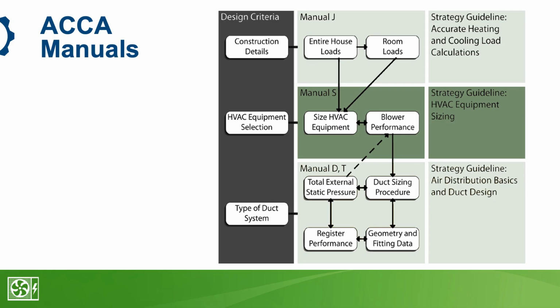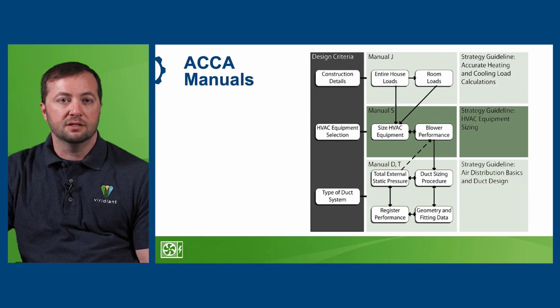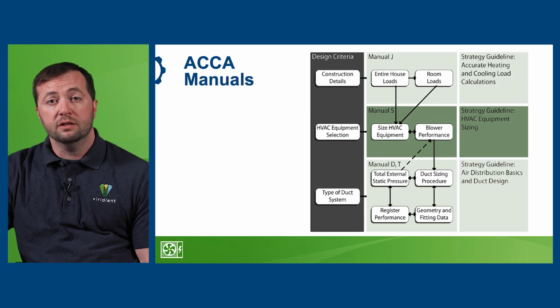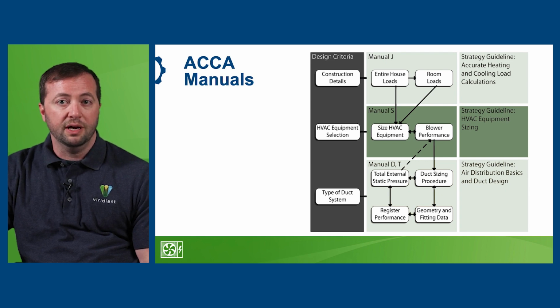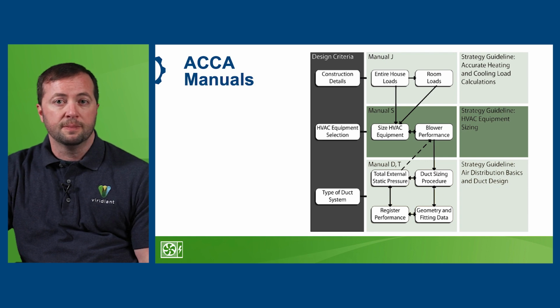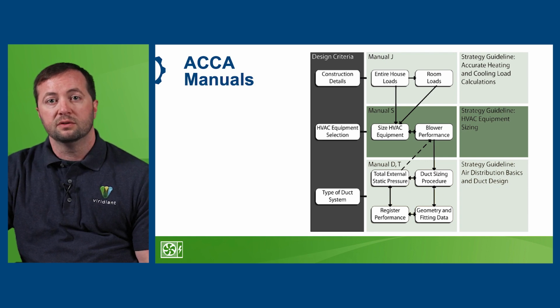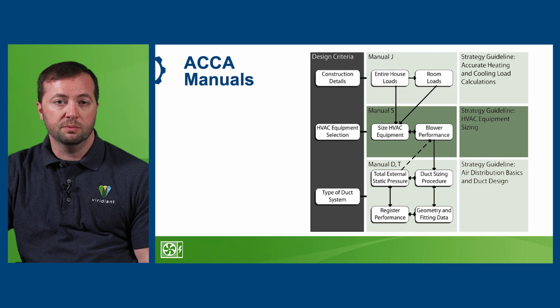It starts with sizing, and that means selecting equipment with heating and cooling output that matches the needs of that specific home. Just choosing equipment based on square footage, or choosing something that seems to be just a little bit bigger just in case, it's not smart. Oversized equipment costs more to install, it doesn't dehumidify as well, and it wears out more quickly, both of those things due to short cycling. Short cycling means that system kicks on, it runs for a very short period of time, and then turns off.